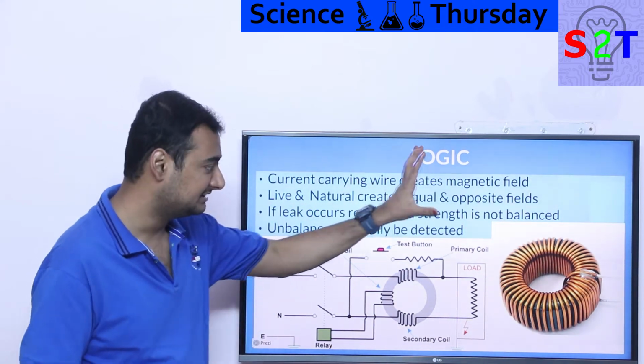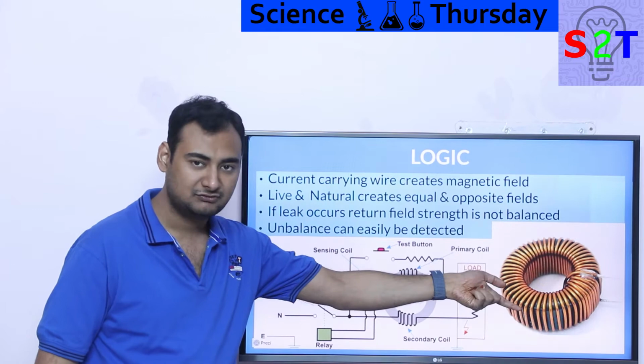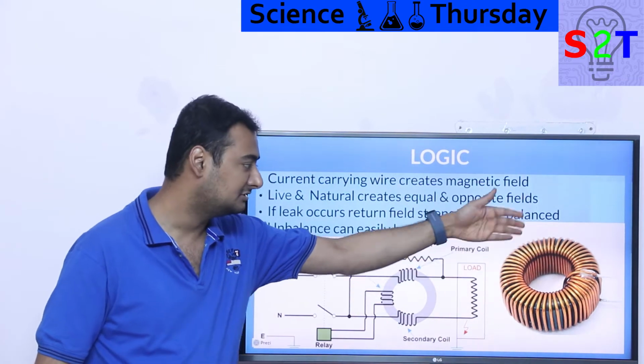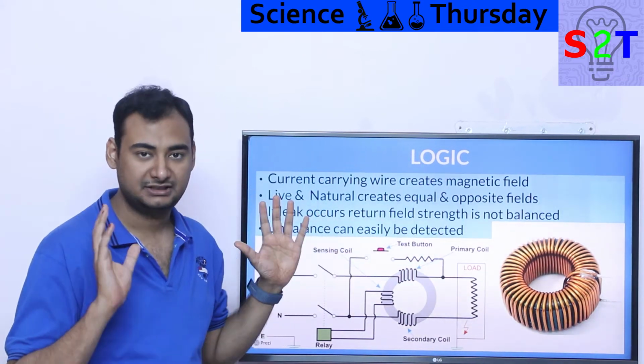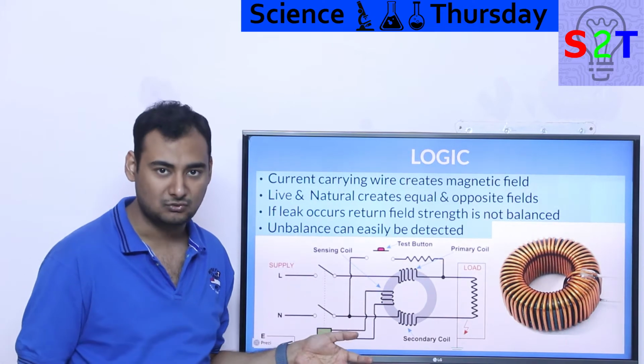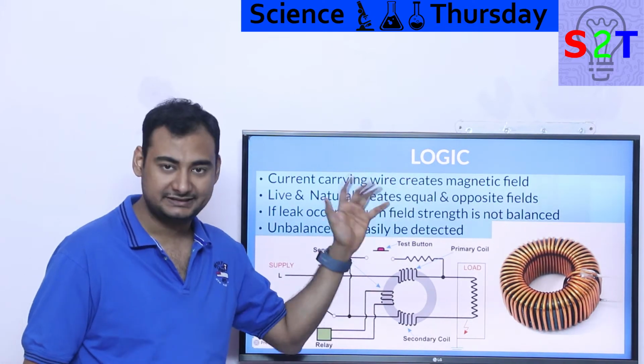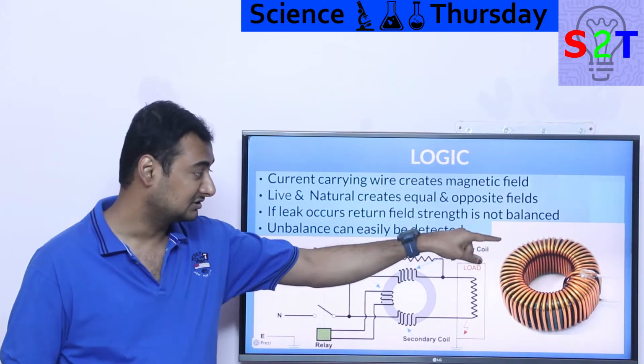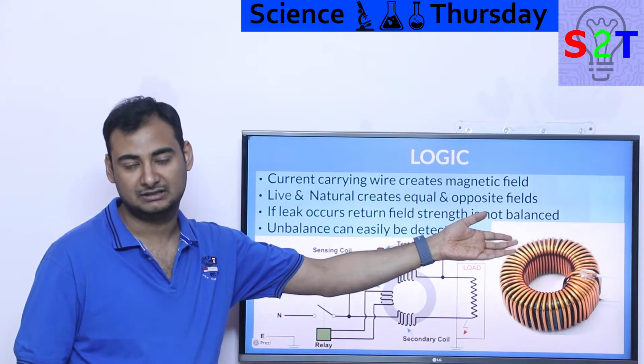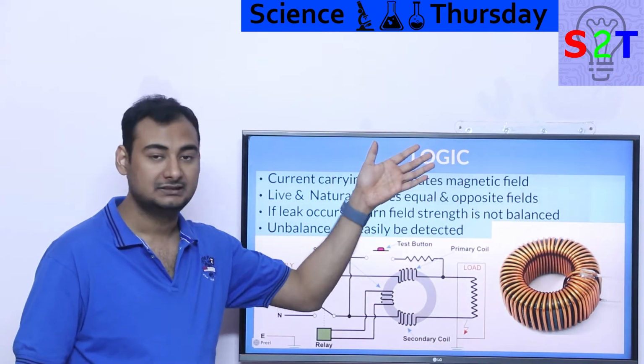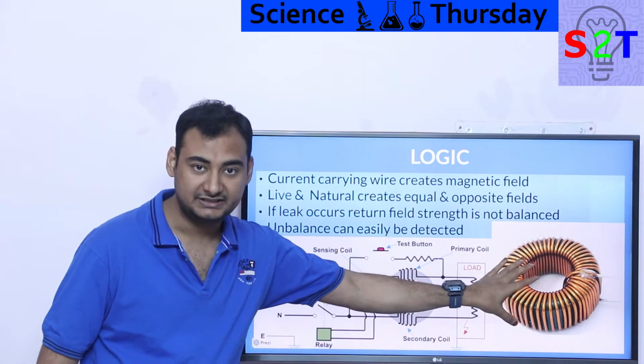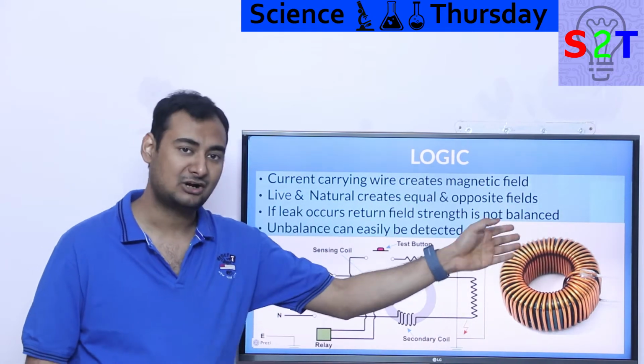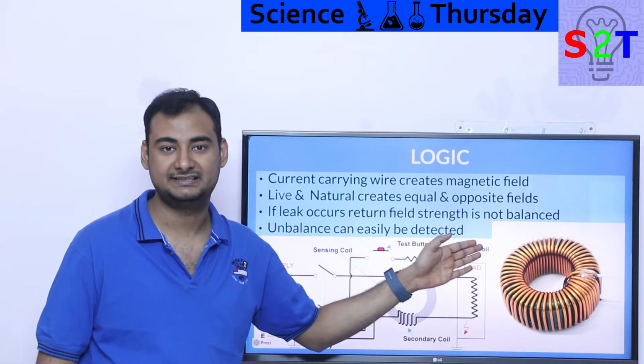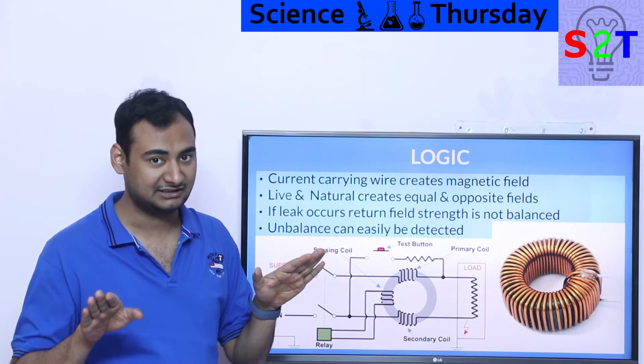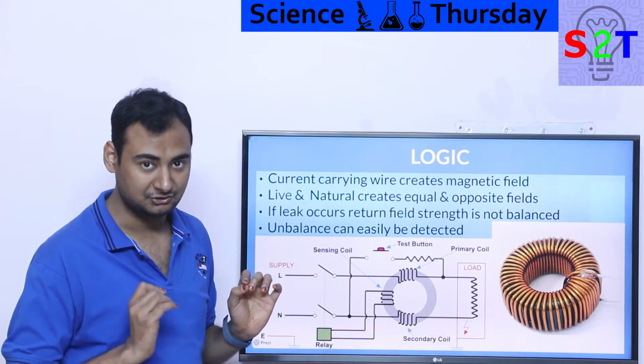What does that mean? That simply means, let's say you put a toroid, you put live on one side, you put neutral on one side. Let's say 10 turns, and you are utilizing equipment, let's say a 100-watt load or 500-watt load or a kilowatt of load. It's going to create a magnetic field. However, because live and neutral are commonly bound to each other, magnetically speaking, they will cancel each other out. So the magnetic flux here would be zero. It does not matter how much you are drawing on the other end, it still would be zero because it's balanced. It's almost like Thanos, perfectly balanced, as all things should be.